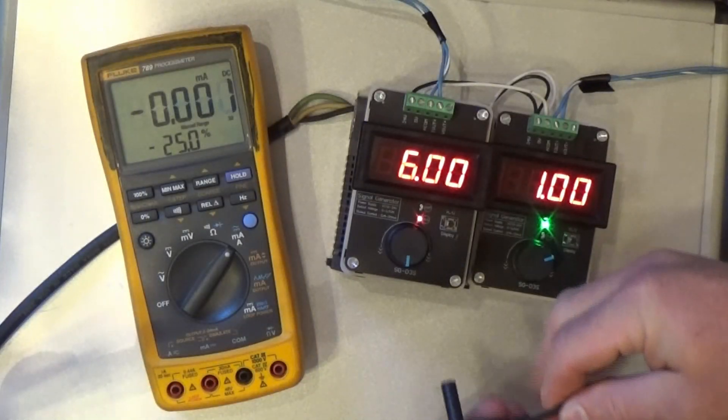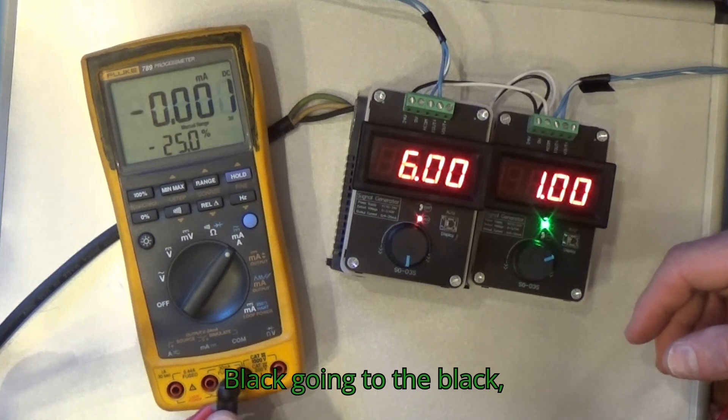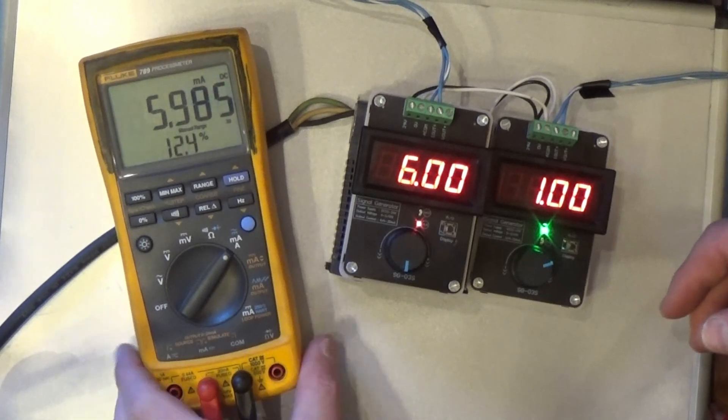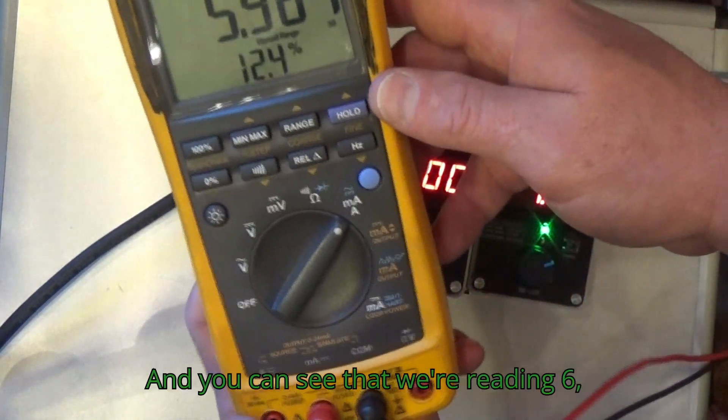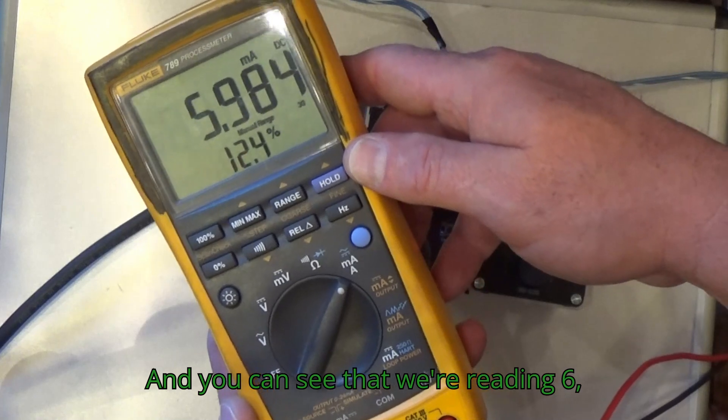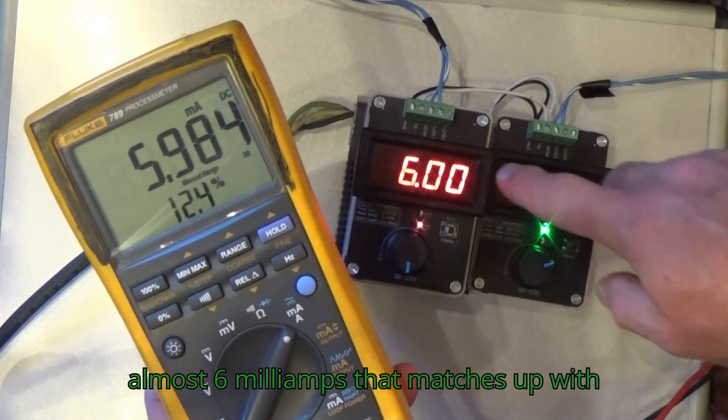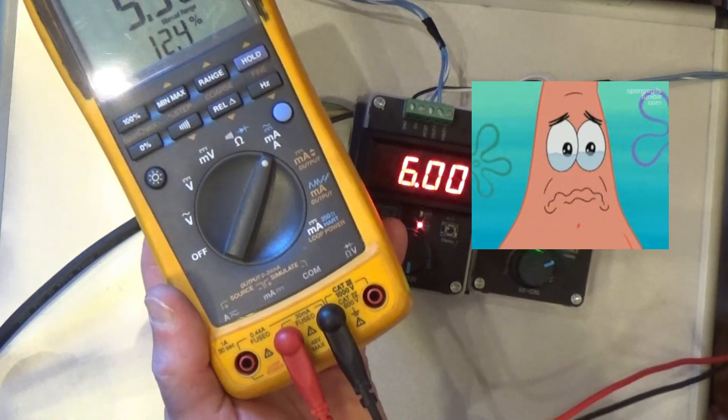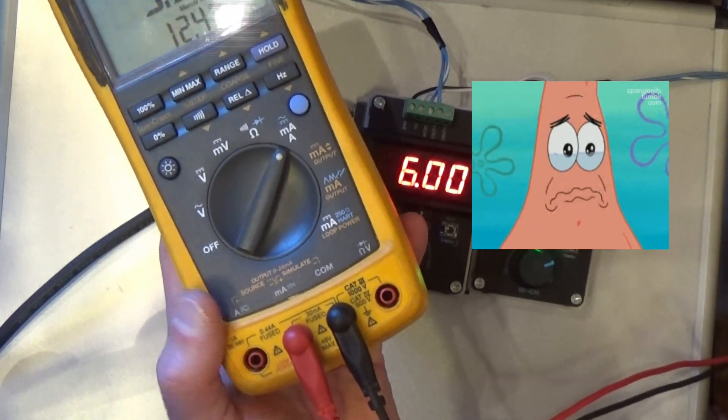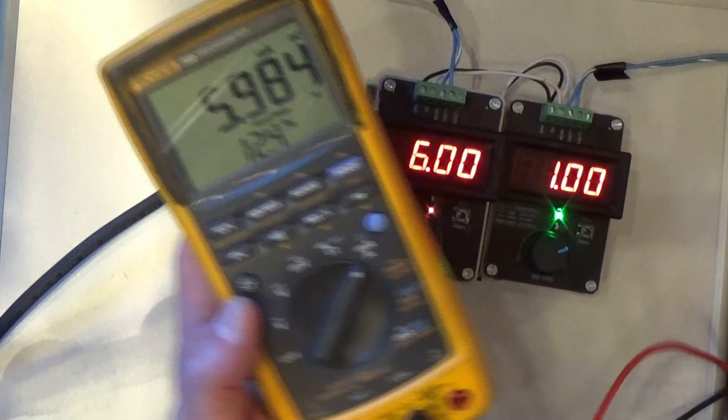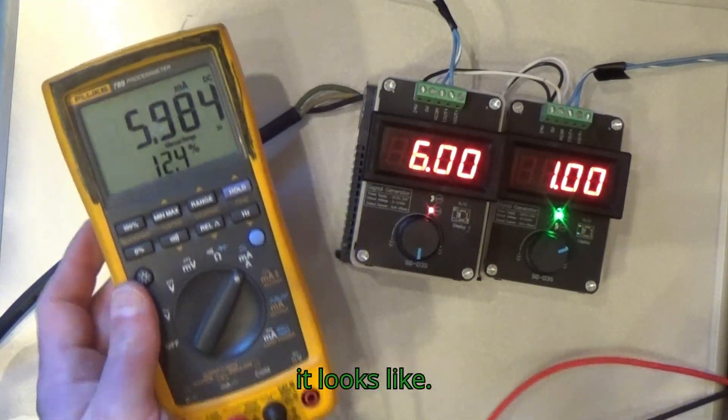Alright, so now we hook up our meter: black going to the black, red going to the red. And you can see that we're reading six, almost six milliamps. That matches up with the six on the transmitter. You notice when I originally described how to hook up those cables, I hooked them up wrong. So even the pros make mistakes at this.